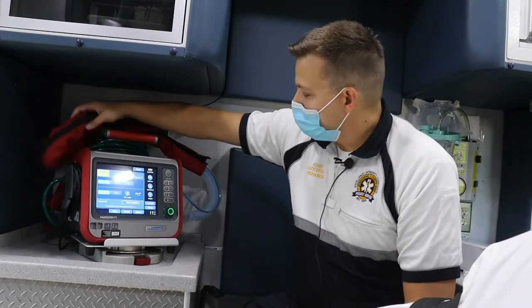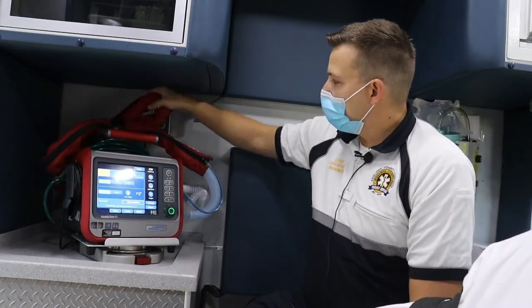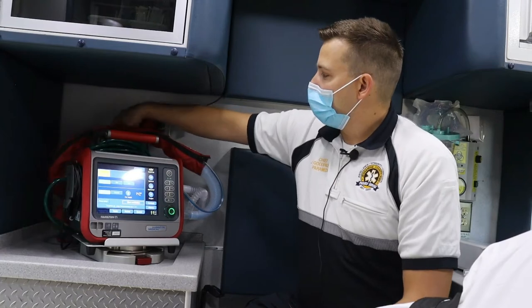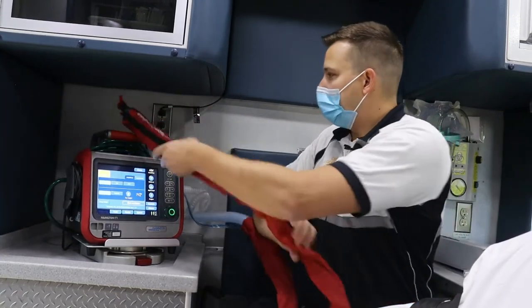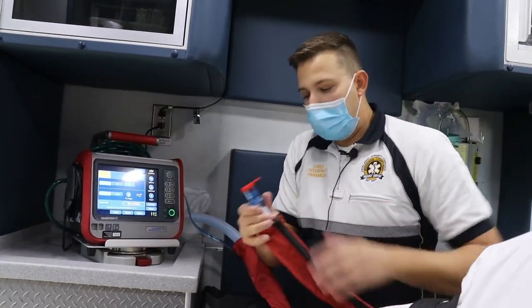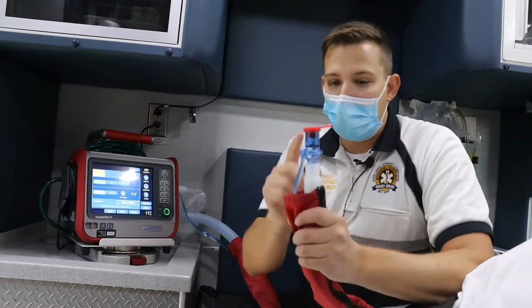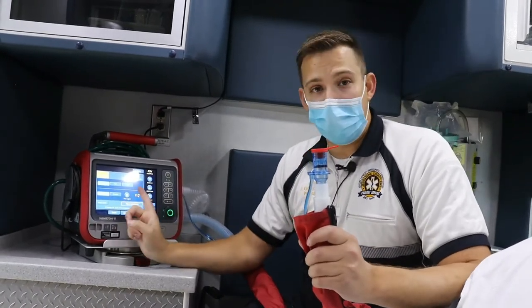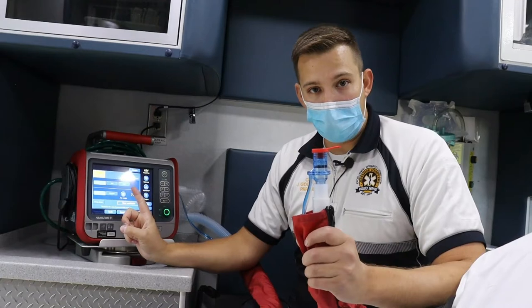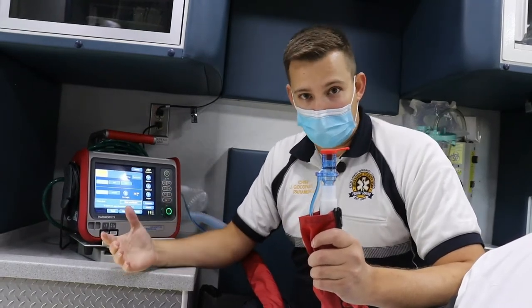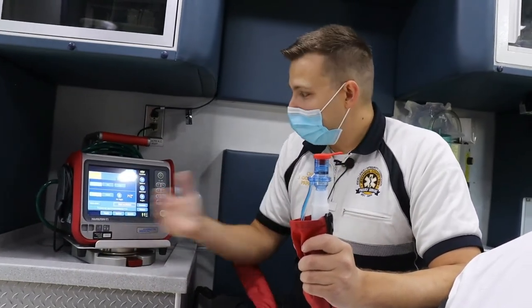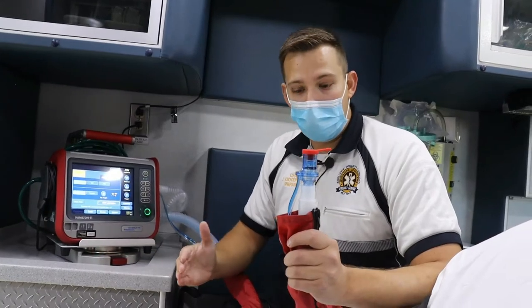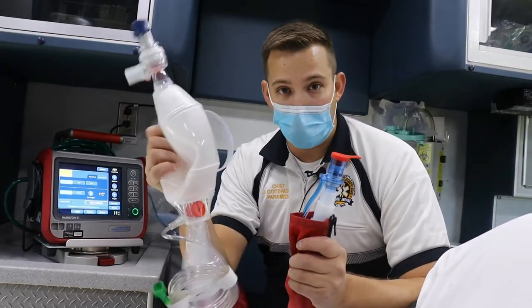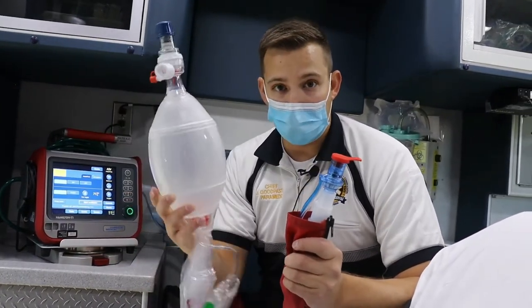In addition, this ventilator is so advanced that there's a valve that goes on the end of it called an expiratory flow valve. This valve tells the ventilator what our lungs are doing, whether they're obstructed or restricted. That tells the ventilator, hey, these lungs don't actually need this much volume, they need this much volume.